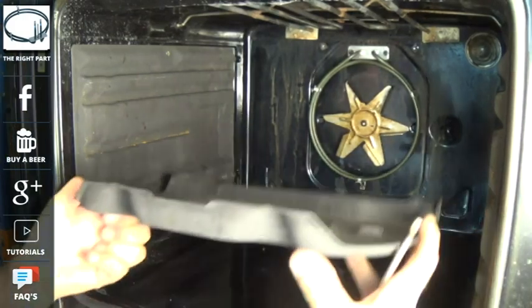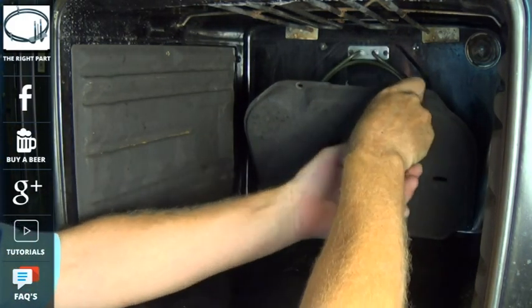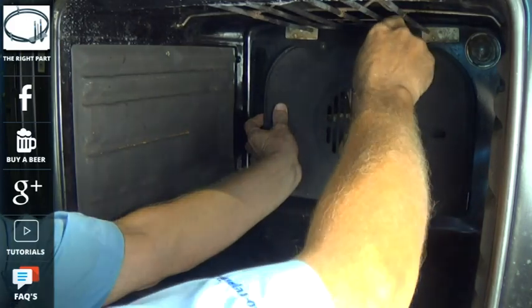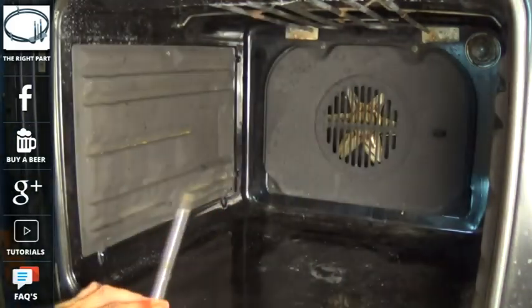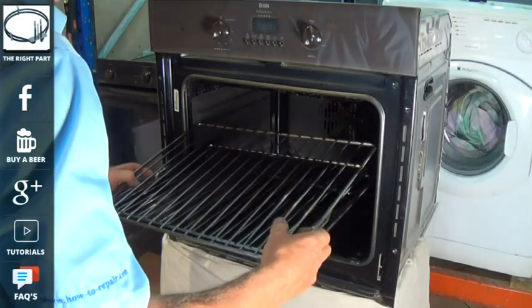A Megger is an insulation testing instrument which is very useful if you're in the trade for measuring the insulation on certain items, especially things like elements, to find out if there's a fault on the element and it's going to earth. The higher the resistance you get, the better the condition of the element.